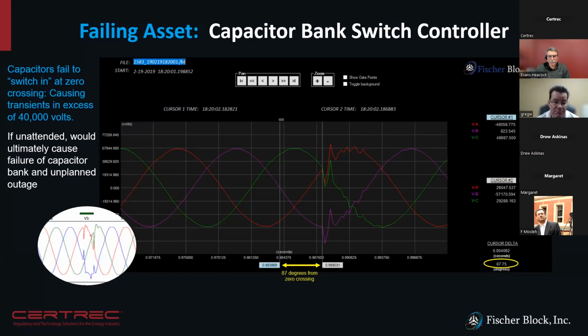And then this is very similar. You talked about a lightning arrestor out on the grid problem that was, I think, part of one of the Odessa events. So this is an indication of a capacitor switch bank controller whereby our platform, doing high resolution continuous monitoring, was able to determine that the capacitor banks were not being switched in and out at zero crossings, which is the intent of a switch bank controller. The timing was degrading in the controller, and capacitors were being switched in and out at points that were not near zero crossings. Therefore, quite a bit of arcing was going on, and that manifests itself in the electrical signals there. And so we were able to provide advanced notice of a problem there to avoid an outage.